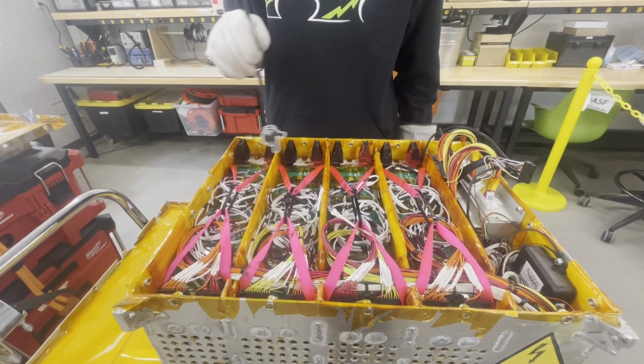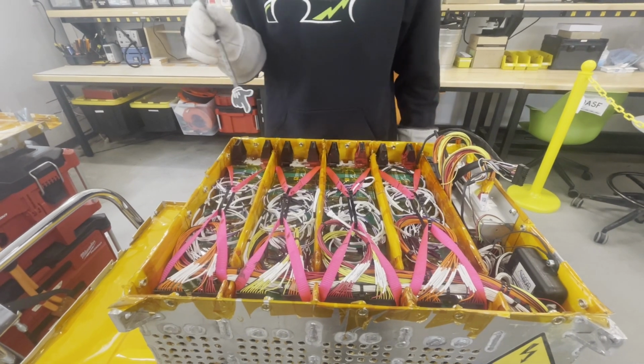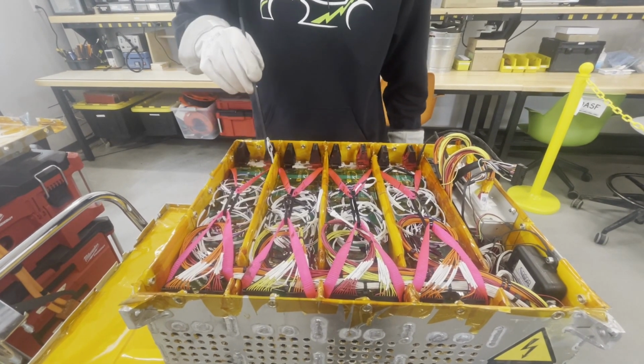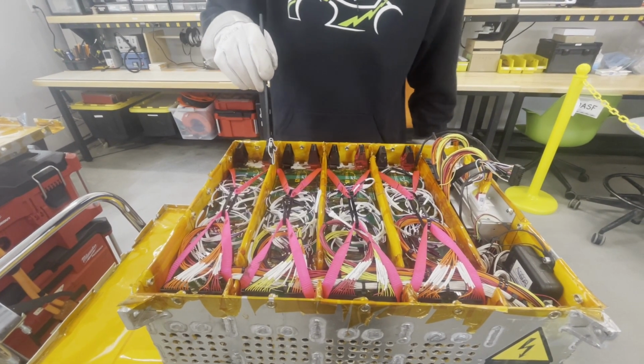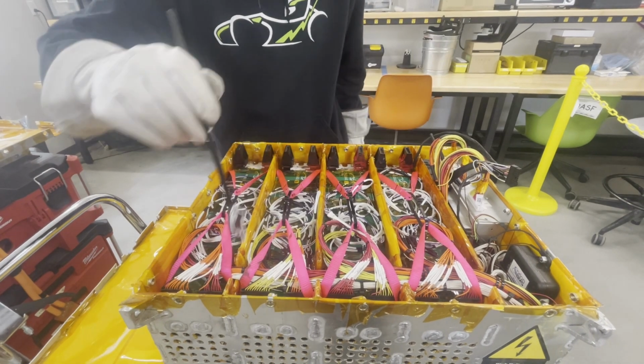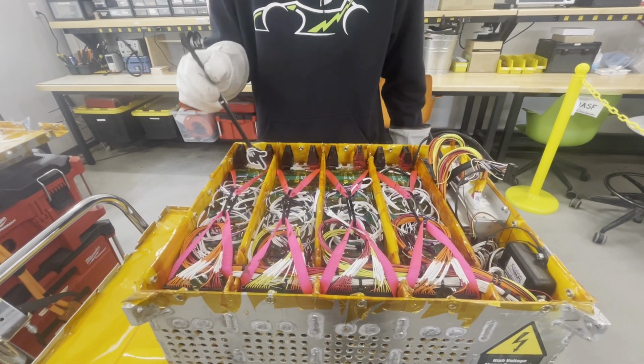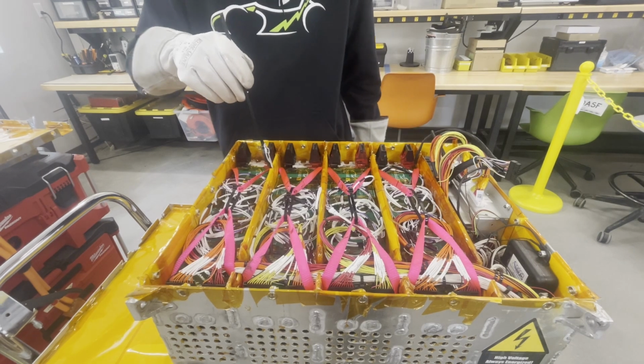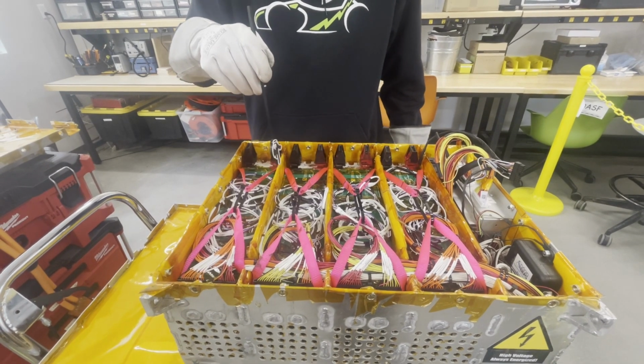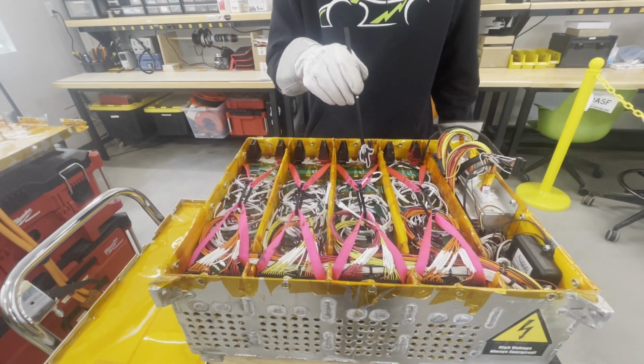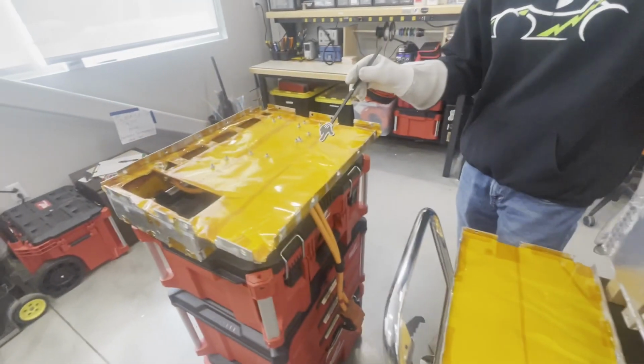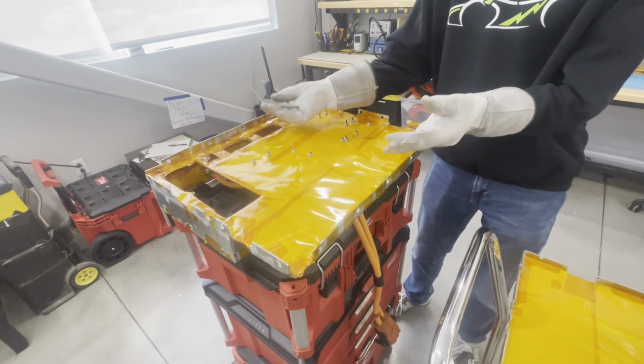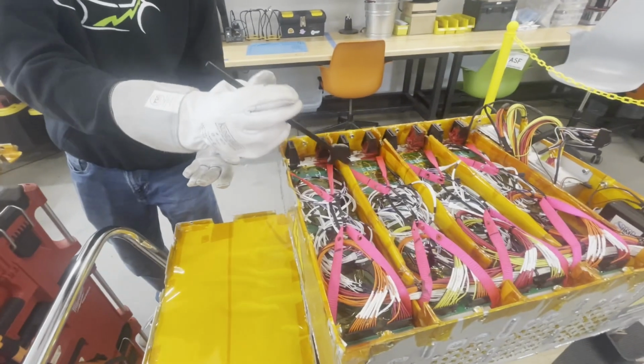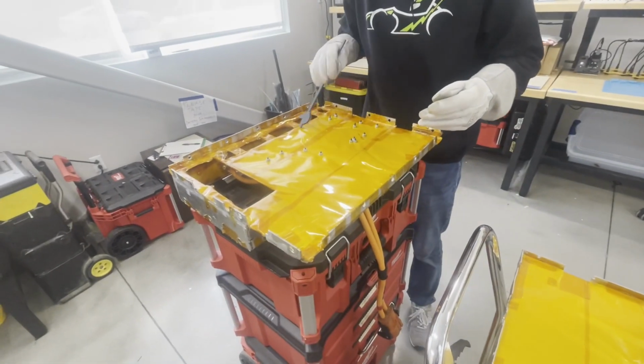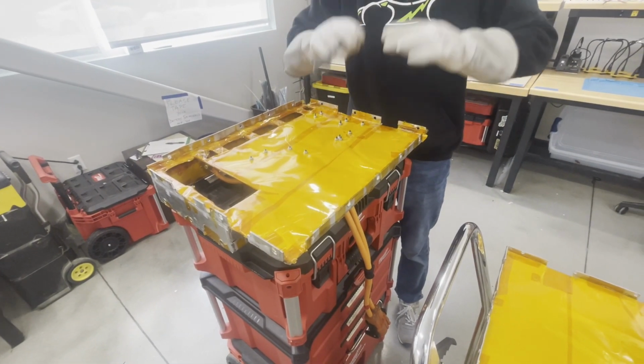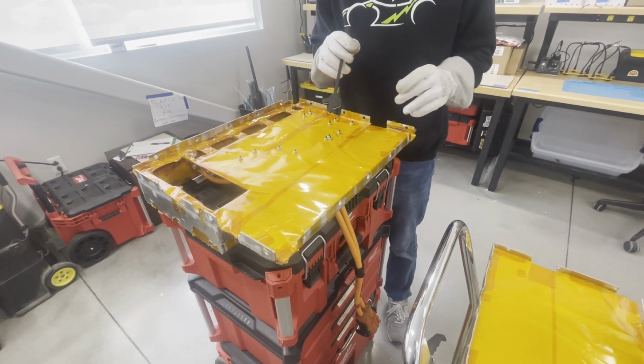Each of our 4 battery modules is separated by an electrically insulative and fireproof material. There is an aluminum wall which is coated again in Nomex 410 and also Kapton tape, which is electrically insulative and fire resistant. And then the bottom of the lid over here, this is the top of this lid would go on top of these right here. You can see it's also covered in Nomex and Kapton, so it completely separates each module from the next module.